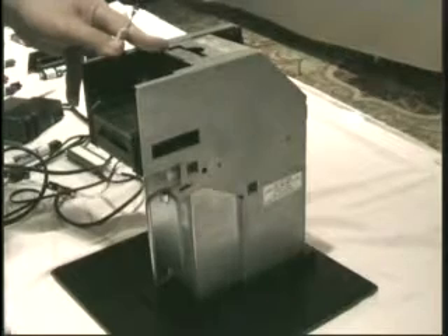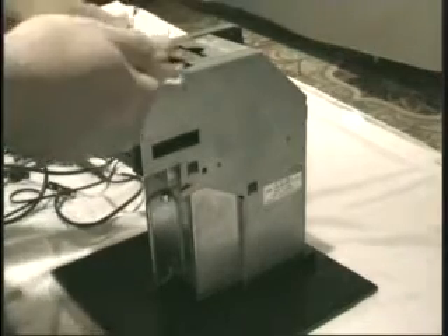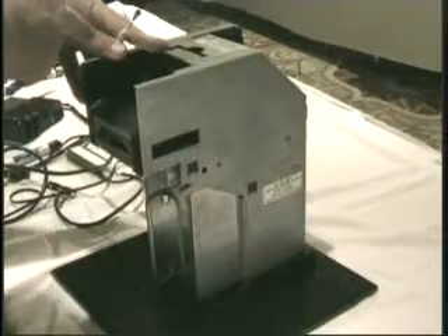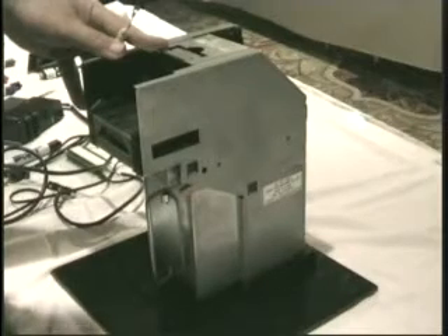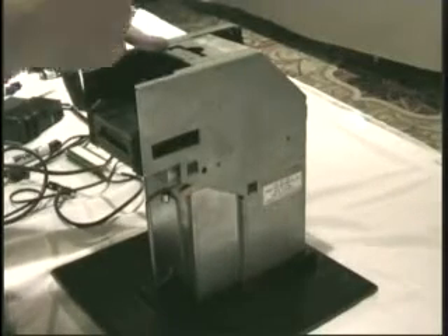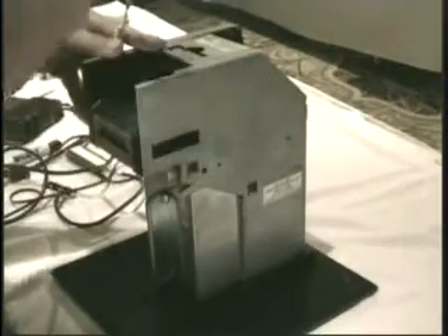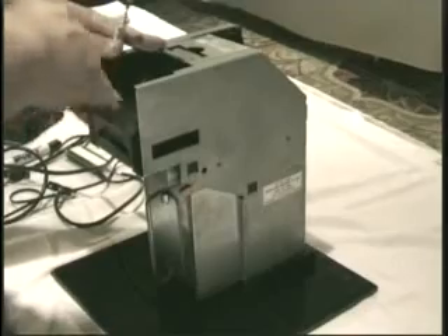That's the only difference. But in this test mode, if you have a failure, if it faults out, take your number of flashes, go to that error table. We had 4 flashes. What's error 4 on table 2? Jam of the transport. I opened up the transport lid. Now you know it's one of those transport sensors. And in a second we're going to get to where the transport sensor test is. You can check each and every sensor in this unit individually. So basically what that's doing is it's breaking it down. It's saying it's in this section here. This is where you want to look. Okay, next test.